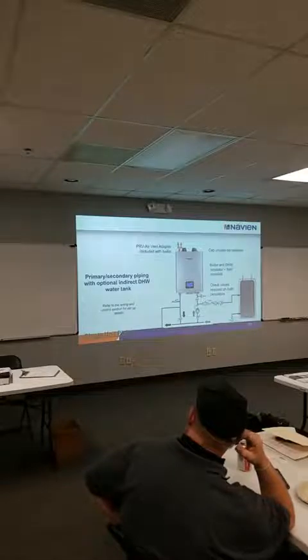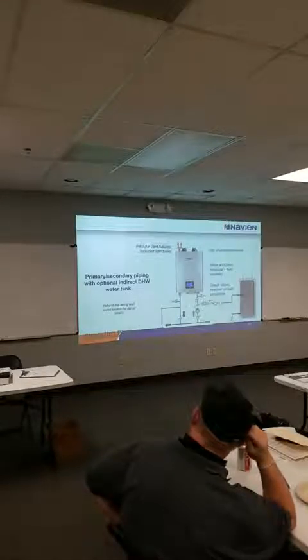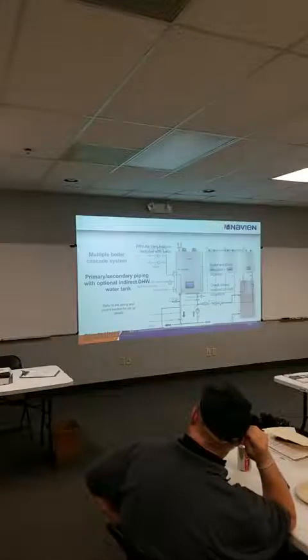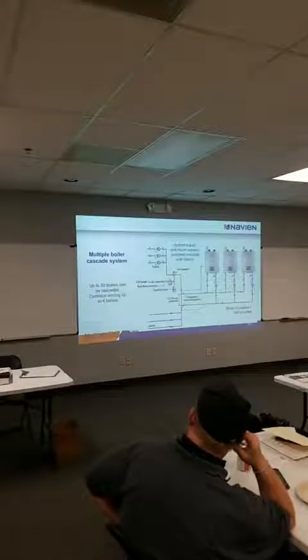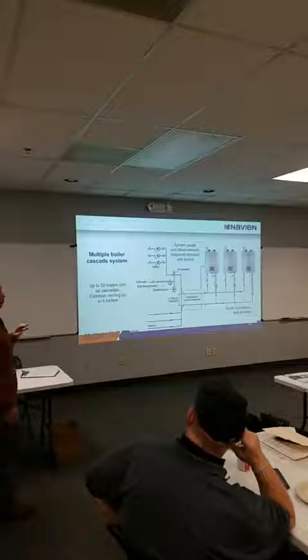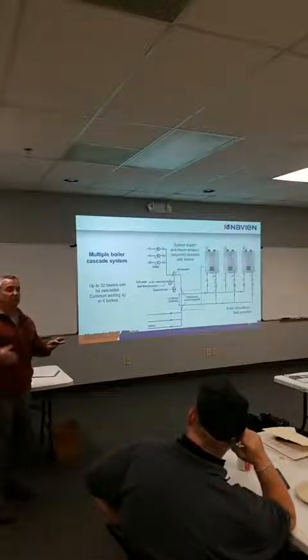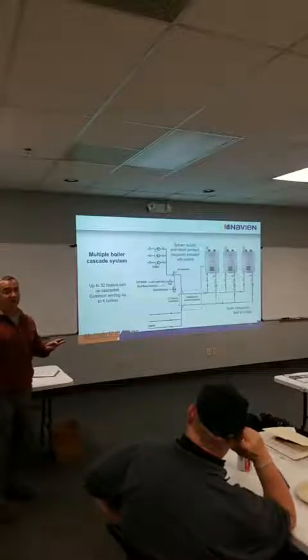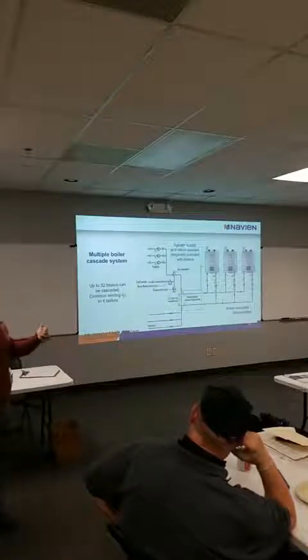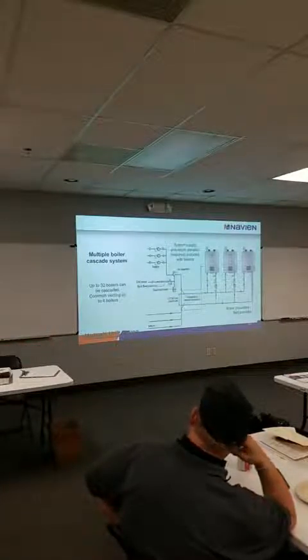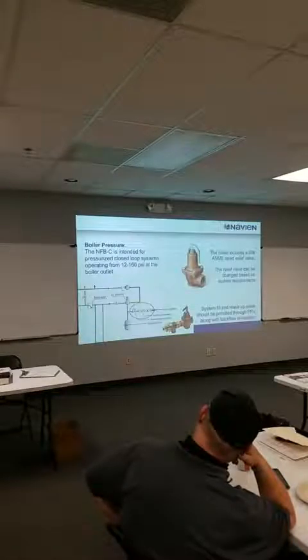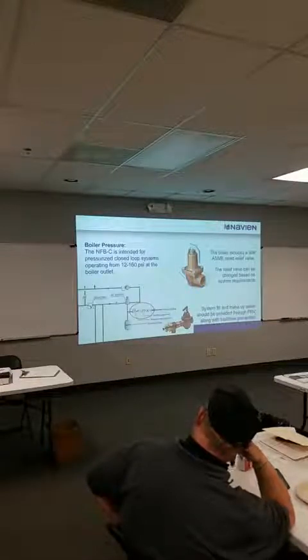That's nice. So, a lot of stuff is gonna look the same as the regular NFB deal that we do. Multiple units, we can common vent up to 4 of the commercial boilers in the system, so we can get up to 1.2 million common vented, but we can cascade up to 32 of these things in the system. And all you need is that communication cable. So you're gonna get a vent damper kit that's gonna come with the cable, it's like $30 extra per unit, there's no other controls you have to buy, everything's built into our standard control.